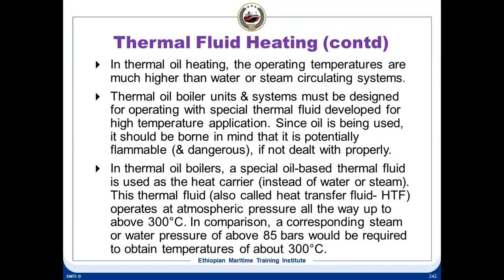So that means this thermal oil has special additives so that the base oil, mainly with the additives, is basically made for high temperature application. Our lube oil is not made for high temperature application. For example, the lube oil cannot function at 300 degrees centigrade. And since oil is being used, it should be borne in mind that it is potentially flammable and dangerous if not dealt with properly.